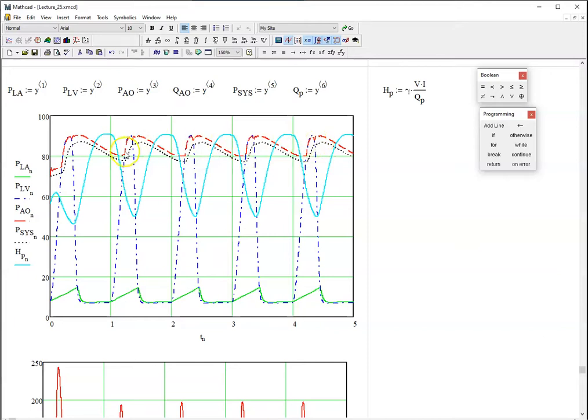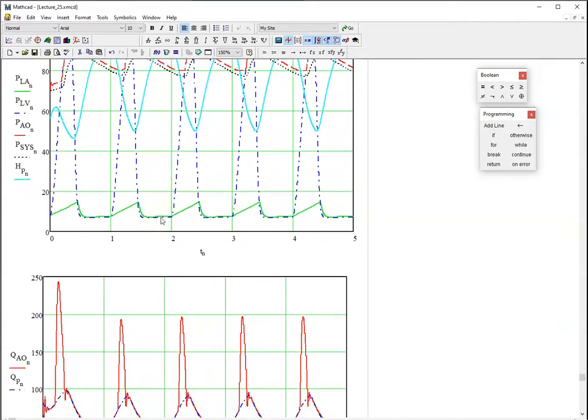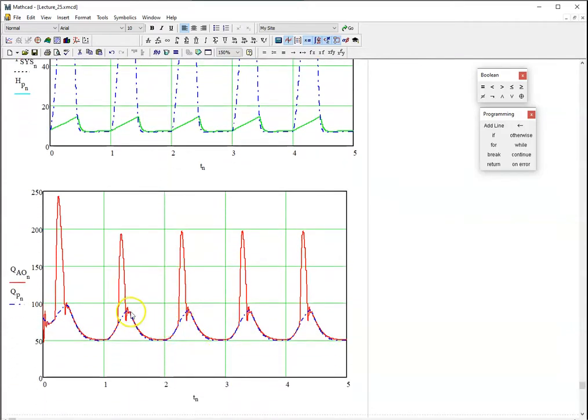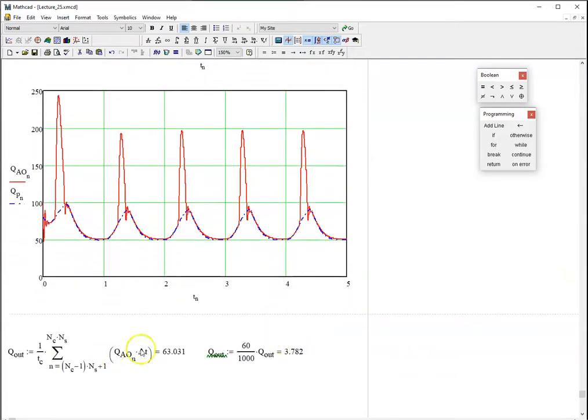It's opening up ever so slightly, just a little bit, for a little bit of the heart cycle — it's opening, but just barely. This is evidenced very clearly in these peaks right here. The red line is the total flow, the aortic flow. The blue line is what the pump is producing. You can see now that the pump is producing quite a bit more flow than before, but the heart is still producing something. You can actually calculate this and update it.